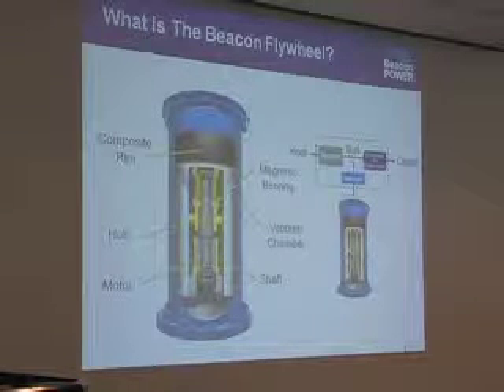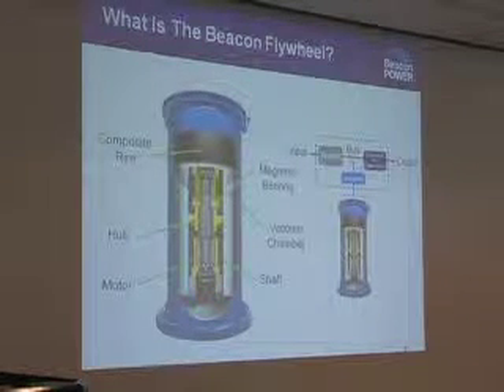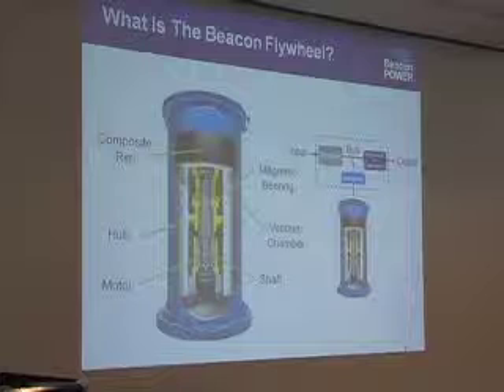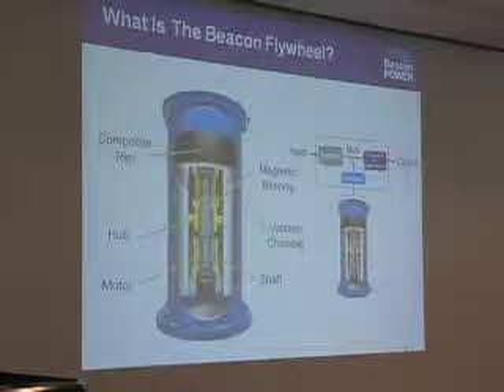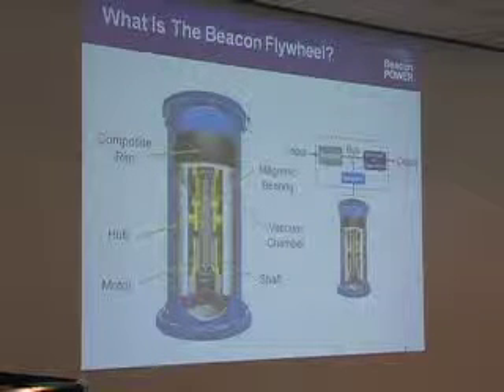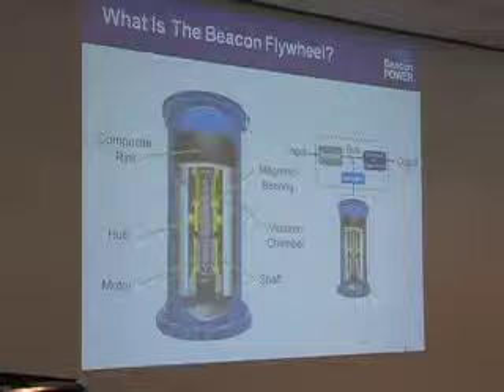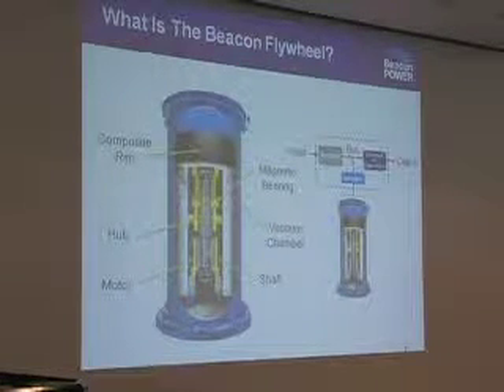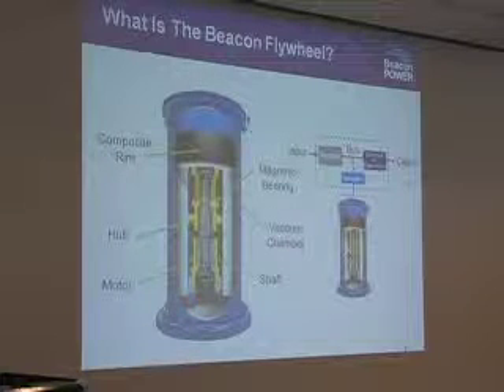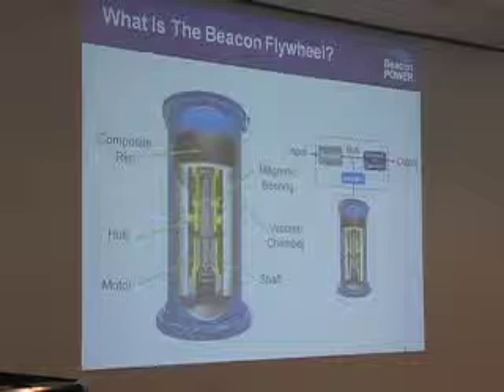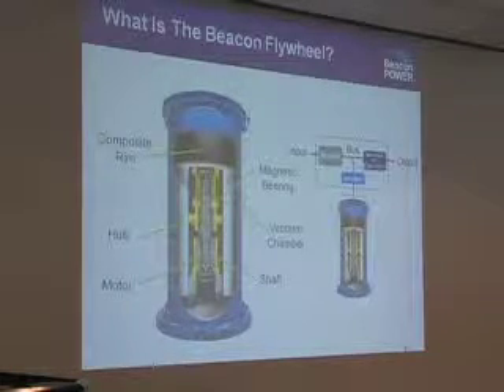We've got a motor generator at the bottom. When there's extra electrons on the grid, it pulls those electrons off and acts as a motor, spinning up the flywheel. When there's a need for electrons, it slows down a little and that motor turns into a generator, dumping electrons back onto the line. The key thing is it really doesn't care whether electrons are coming in or out, it can go up and down, and it can do a full charge-discharge cycle in under 4 seconds, making it a very fast-response asset.